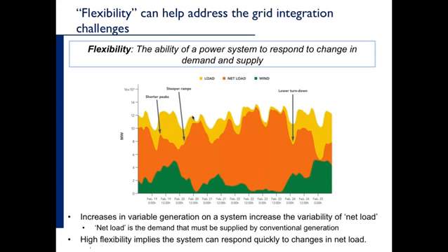But if we have a lot of wind, the wind allows us to turn down the generation, the thermal generation, but we have a ramp that goes from somewhere around 7,000 megawatts or even a little bit less than that, all the way up to just over 10,000 megawatts. So we have steeper ramps. That means that our conventional generation has to be more nimble. It has to move faster and further than it did in the no wind case.